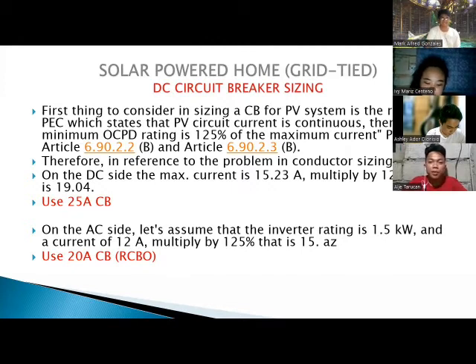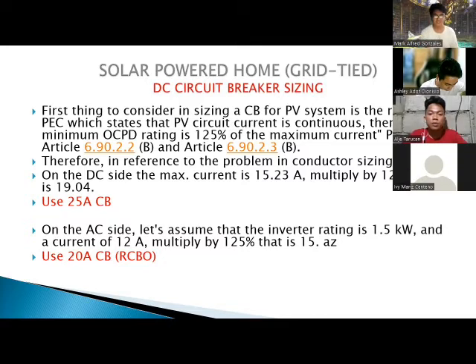This is the DC circuit breaker sizing. First thing to consider in sizing a circuit breaker for a PV system is the ruling in PEC, which states that PV circuit current is continuous. Thereby, the minimum OCPD rating is 125% of the maximum current, per PEC 2017 Article 6.90.2.2 B and Article 6.90.2.3 B. Therefore, this is the reference of the problem in conductor sizing.